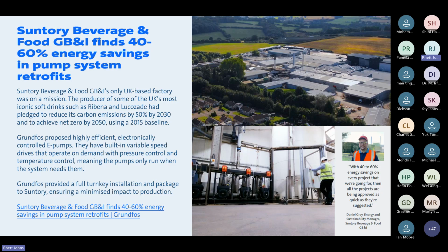So we used our IE5 motors, which have built-in variable speed control, and they operate on demand with the pressure control and temperature control depending on the application, meaning that the pumps only run when the system needs. So we provided a full turnkey installation and package to Suntory, and this resulted in between 40 and 60% energy savings with every project that they were looking at that we had suggested. And they've just moved throughout the site's different areas to optimize the pump systems within the factory.